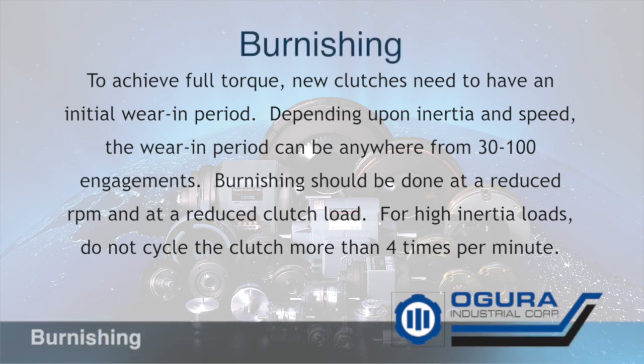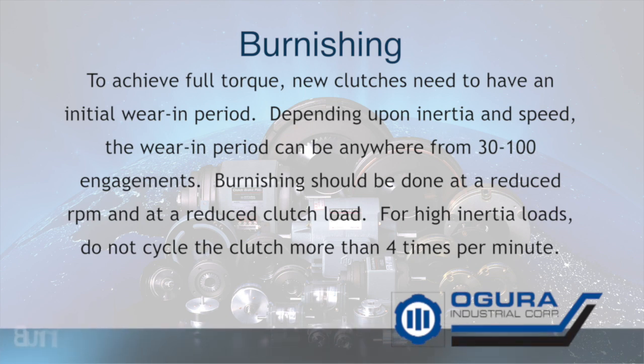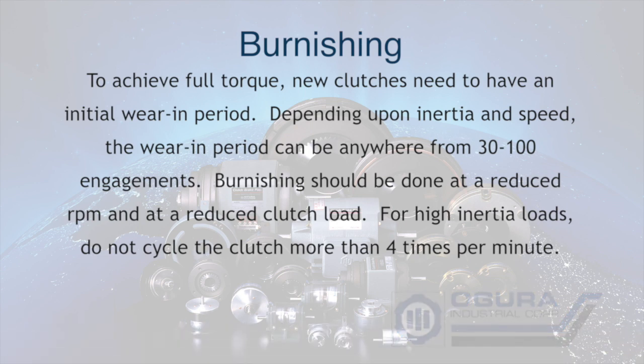To achieve full torque, new clutches need to have an initial wear-in period. Depending upon inertia and speed, the wear-in period can be anywhere from 30 to 100 engagements. Burnishing should be done at a reduced RPM and at a reduced clutch load. For high inertia loads, do not cycle the clutch more than four times per minute.